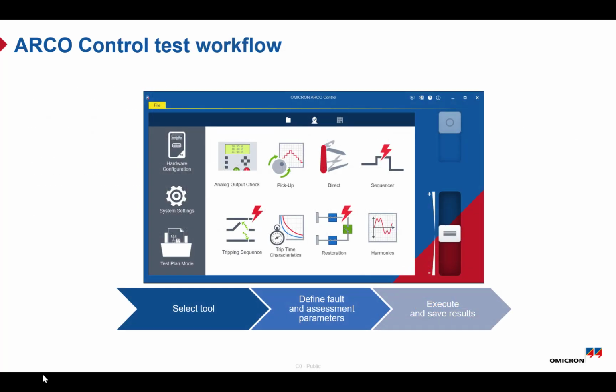Next, we will go through the ARCO Control test workflow. ARCO Control is the software used with the ARCO 400, and it's specifically designed for testing recloser and sectionalizer controllers. It's a free software that you can download from the Omicron customer portal and install on a Windows PC. The main goal of this software is to make testing simple and fast, especially for field applications. It provides step-by-step guidance through the testing process, so you don't need to remember every detail. The software leads you through each test. Once the test is completed, the results are generated quickly and can be exported into an HTML or PDF report.